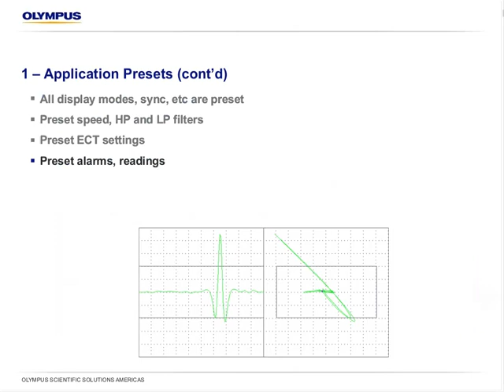What's preset actually is all the display modes, the synchronization, the speed, the high pass and low pass filters, the eddy current settings, frequency, probe drive, all that. The alarms, if you need them, they're preset. If you don't like them, you just turn them off. It's faster than adjusting the box if you need it. The readings, all that is preset.